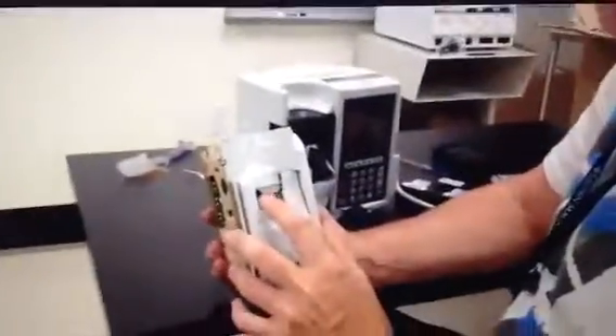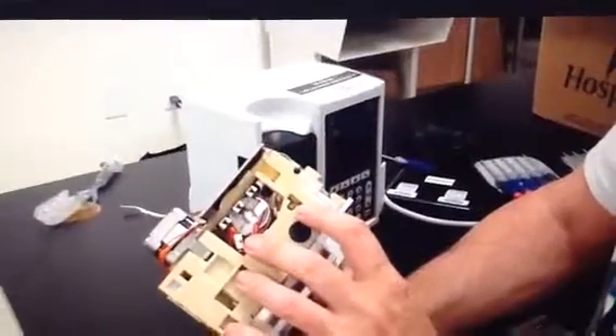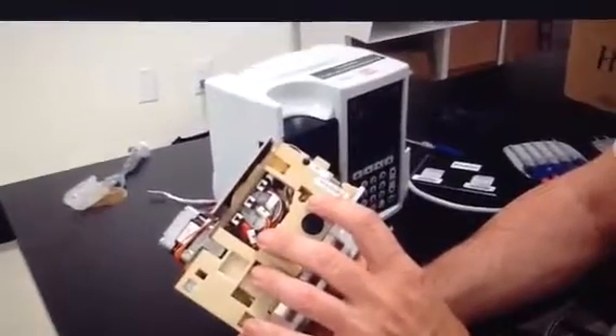Calibrated. And you know it needs calibrating because of the performance verification testing that you do during PM, preventative maintenance. You test pressures. You test the pressure at 6 psi and 10 psi, and that's pounds per square inch. You also test if it detects air in line, and if it does not detect air in line, then you need to calibrate the air sensors. So these pots on the side of the pump here are for calibrating your distal and your proximal pressure.